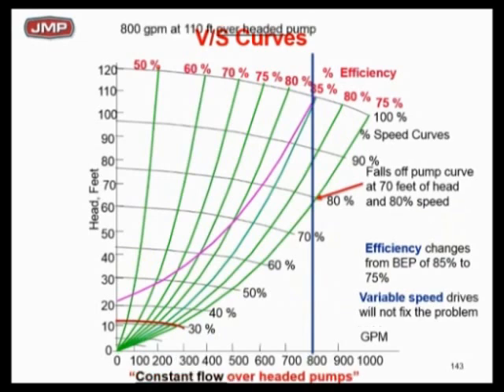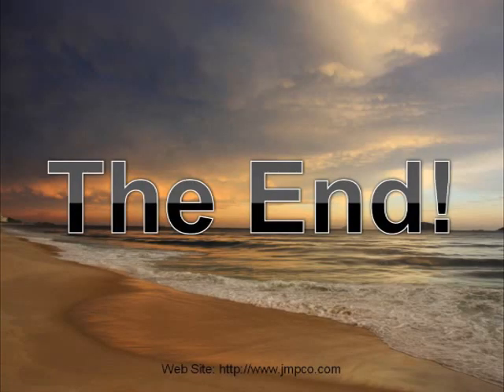Here's where the pump falls off the curve — the selection is 800 GPM, 110 feet of head. A variable speed drive will not fix this problem. If you insist on picking a pump that's over-headed, a variable speed drive is not going to fix it. You're going to have to throttle that pump to get it back up on the curve, and at that point you've broken the energy code.